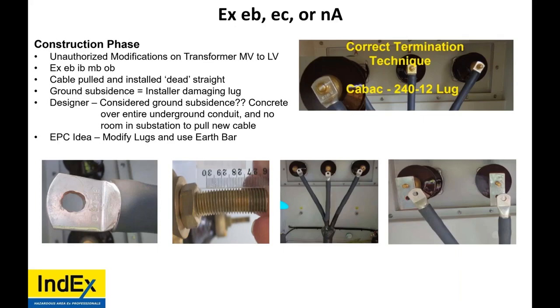So when we look at the top right-hand side, this is how it was done correctly. But unfortunately, the designers did not account for the 100 or 150 millimeters of ground subsidence. The structure was sinking. Now, the cable went straight down the cable tray into a conduit in concrete that went all the way over to a substation that was also on concrete, and there was no space under the substation. So you could not replace the cable. The after effect, I will not show that picture, but it was not pretty.